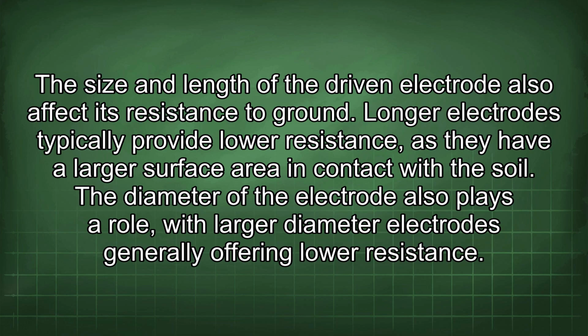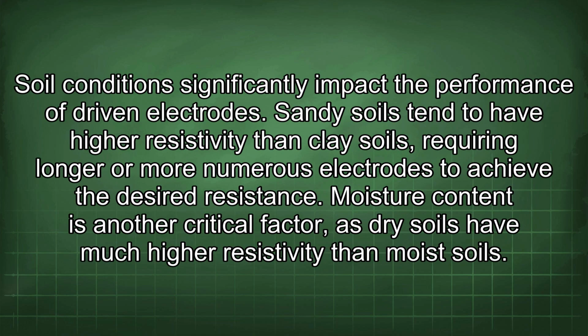The size and length of the driven electrode also affect its resistance to ground. Longer electrodes typically provide lower resistance, as they have a larger surface area in contact with the soil. The diameter of the electrode also plays a role, with larger diameter electrodes generally offering lower resistance. Soil conditions significantly impact the performance of driven electrodes. Sandy soils tend to have higher resistivity than clay soils, requiring longer or more numerous electrodes to achieve the desired resistance.